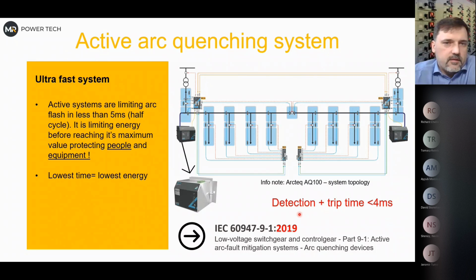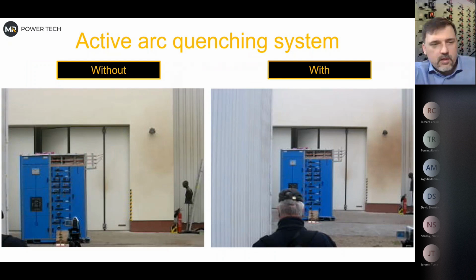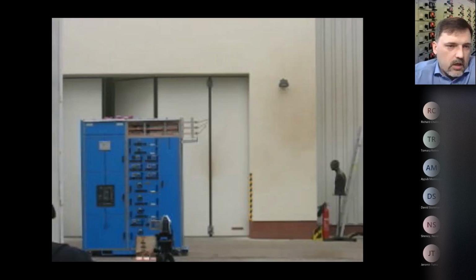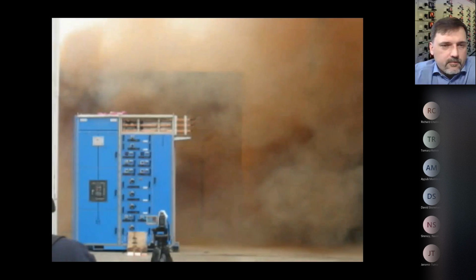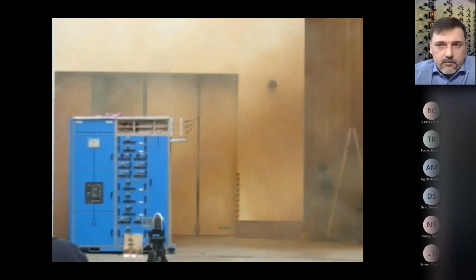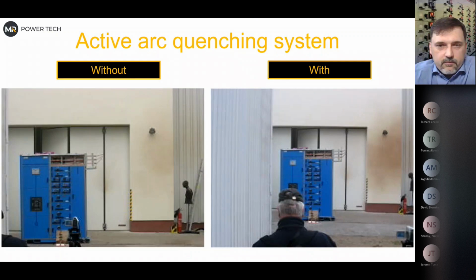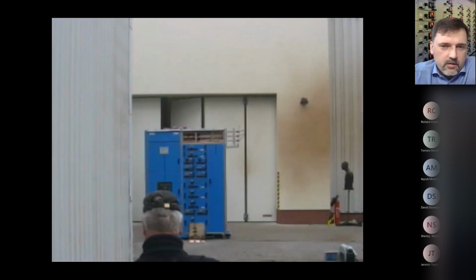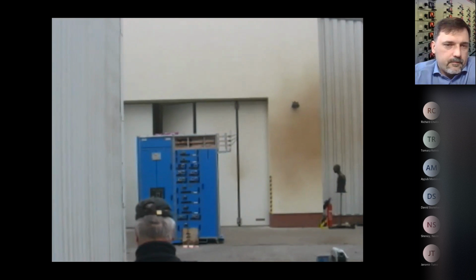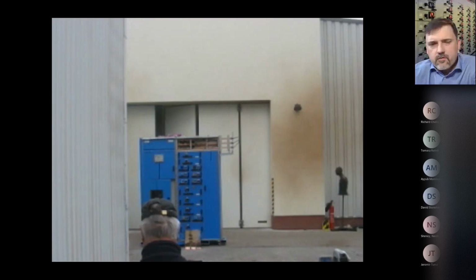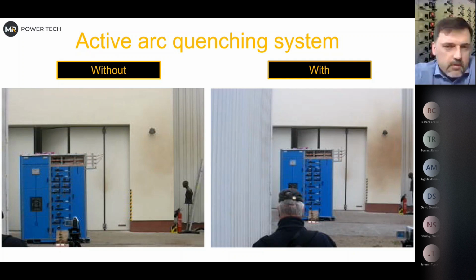And then we have to send the signals to trip the energy, because our system can withstand the 3-phase bolted fault, but not the arc fault. So the best way is to show you this. That's how it looks without the quencher. Yeah, that's what it is. And if we have the system activated, we try to do the same. That was a test from a test lab in Berlin.